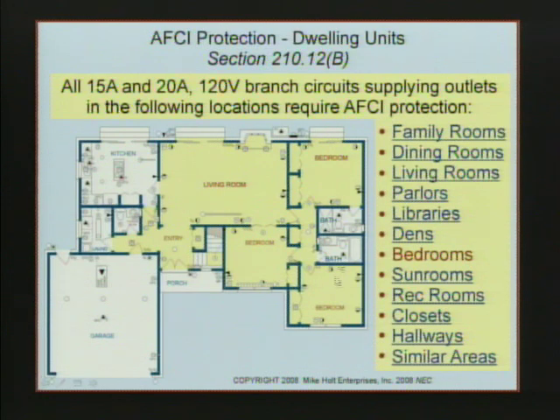You got AFCI protection the whole house, but not the kitchen lights, not the bathroom lights, not the laundry lights, not the garage lights. But then the code does say similar areas. So probably the easiest way is to simply do what? Just make sure all the lighting is going to be on the AFCI protected circuit, except the receptacles that are GFCI won't be on the AFCI protected circuit.